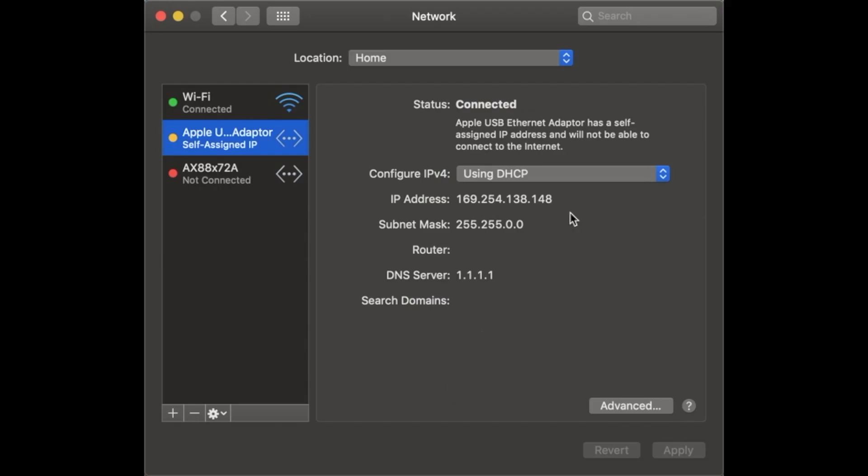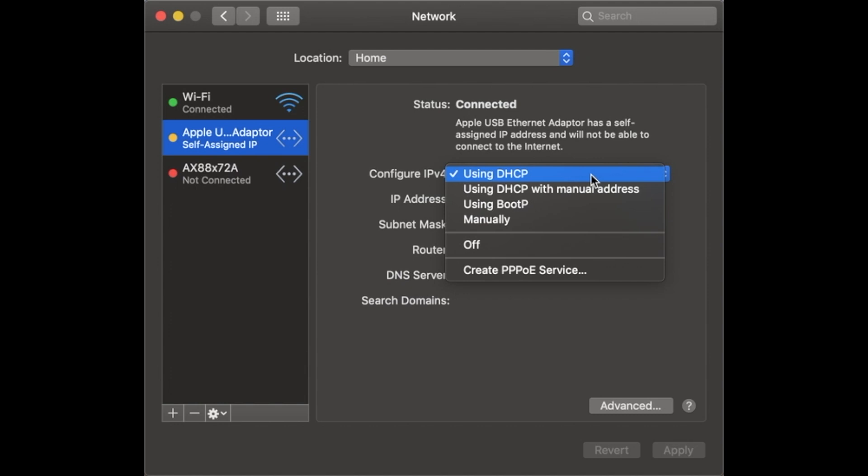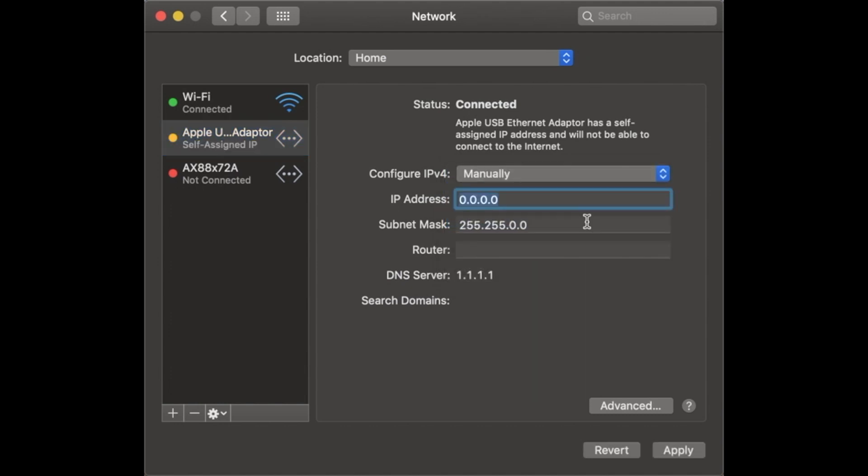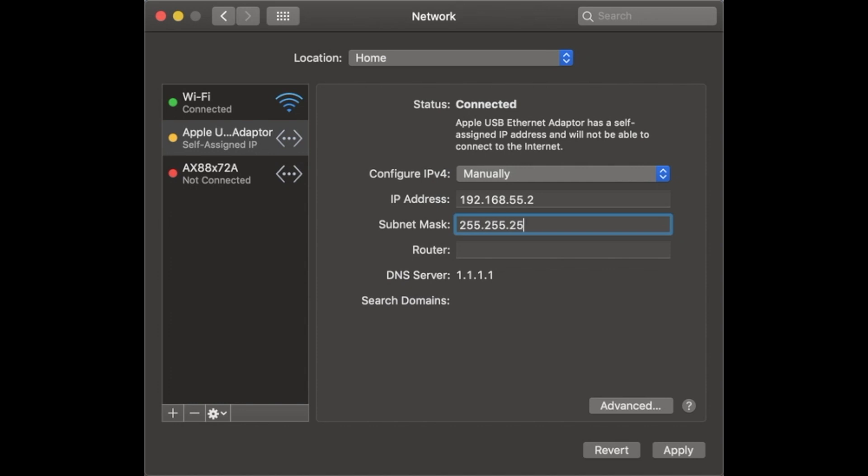In order to connect to the smart logger you need to connect the cable directly between your computer, your Ethernet cable and your PC and put an IP address manually into your PC within the same range as the smart logger has been set to but not the same address. So in this case .2 is slightly different.